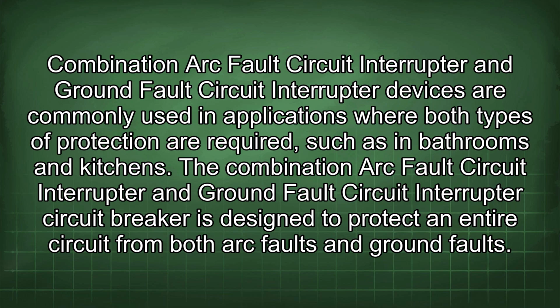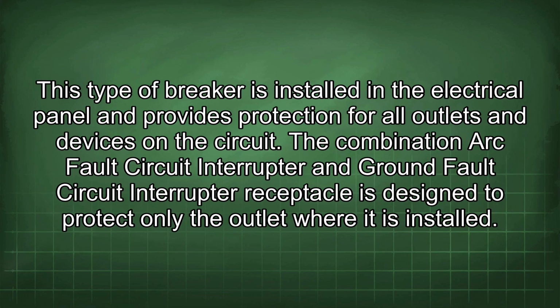Combination arc fault circuit interrupter and ground fault circuit interrupter devices are commonly used in applications where both types of protection are required, such as in bathrooms and kitchens. The combination circuit breaker is designed to protect an entire circuit from both arc faults and ground faults. This type of breaker is installed in the electrical panel and provides protection for all outlets and devices on the circuit.